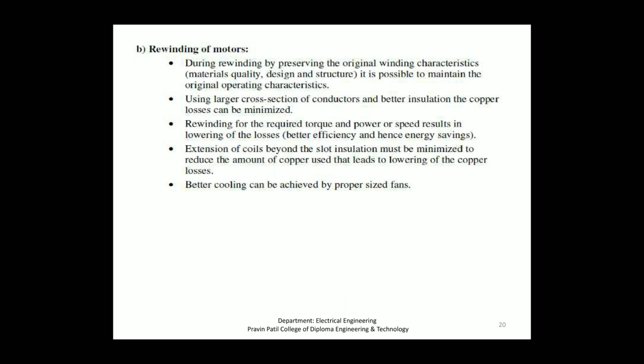During rewinding, by preserving the original winding characteristics, that is the material quality, design and structure, it is possible to maintain the original operating characteristics. Using a larger cross section of conductor and better insulation, the copper losses can be minimized. Rewinding for the required torque, power or speed results in lowering of the losses, better efficiency and hence energy savings. Extension of the coil beyond the slot insulation must be minimized to reduce the amount of copper used, which leads to lowering of the copper losses. Better cooling can be achieved by a proper size fan.